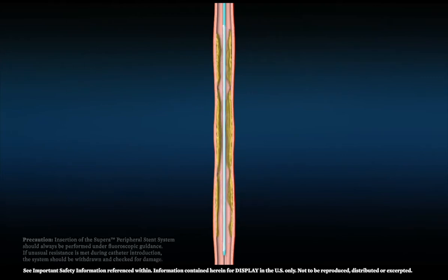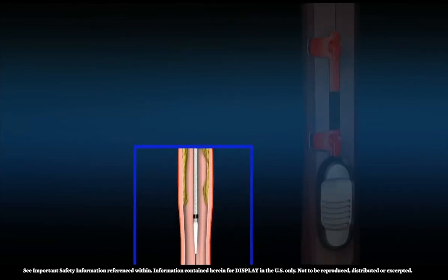Prior to use, Supera should be removed from its packaging, inspected for bends or kinks, flushed and wiped per the instructions for use. The Supera catheter should be introduced into the sheath utilizing a 0.014 inch or 0.018 inch guide wire. Advance the system until the distal sheath marker and the stent length marker encompass the target lesion.